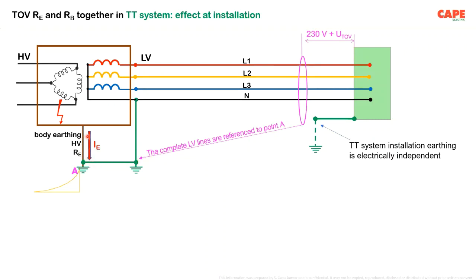Let's say, for example, the fault current is 5 kiloamperes, and the earth electrode resistance is, let us say, 5 ohm. So 5 kiloampere into 5 ohm, approximately 25 kV will be the peak of the voltage gradient. Now the line and neutral are stressed or referenced to this 25 kV. That means the line and neutral are at 25 kV, whereas the body of your electrical installation is connected to an electrically separated place. As a result, this one is at zero potential.